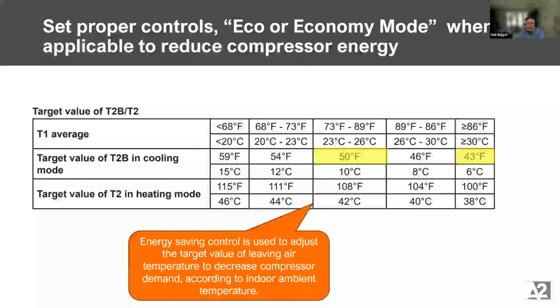And then the last thing that's kind of a function of VRF is there are a lot of control options, and different manufacturers call it eco mode or economy mode. And I would say this really is something that should be focused on. It has to be for the right applications, but especially in a climate like Idaho where it's drier, the ability for the system to relax its refrigerant temperatures and not operate at the extremes when it has to is really the magic that saves a lot of energy. So even having that configured when a system is installed can be critical.